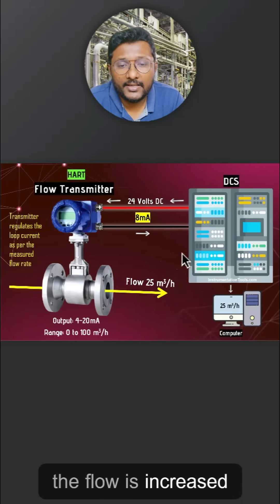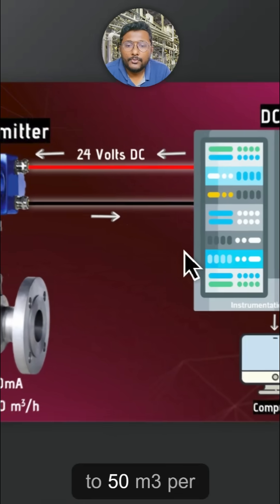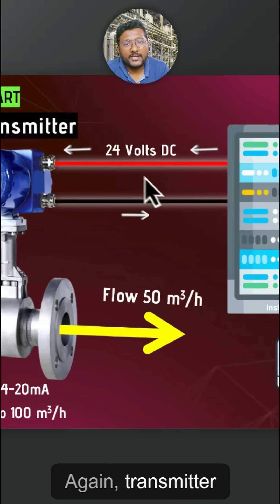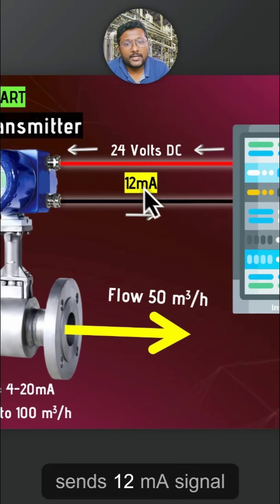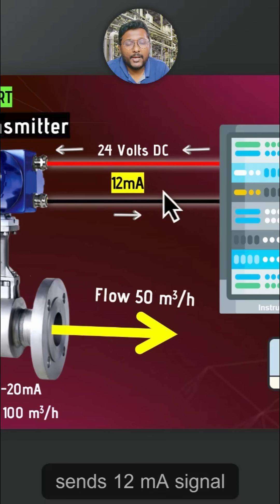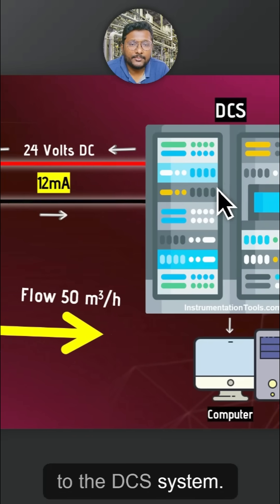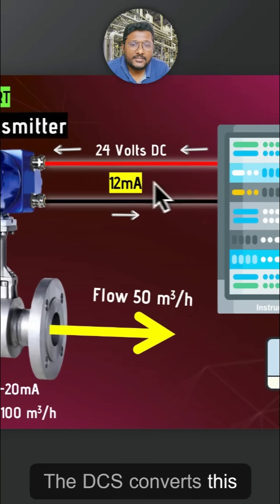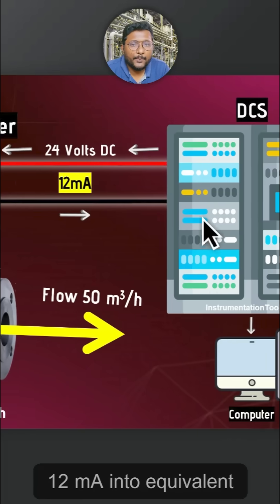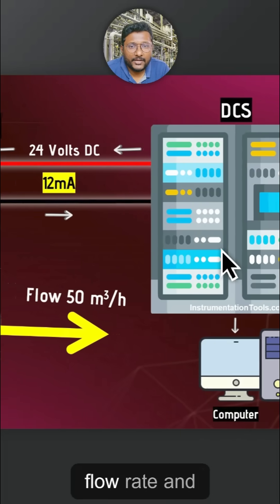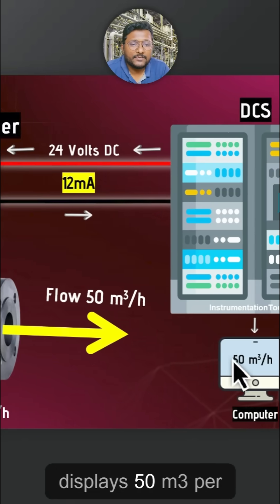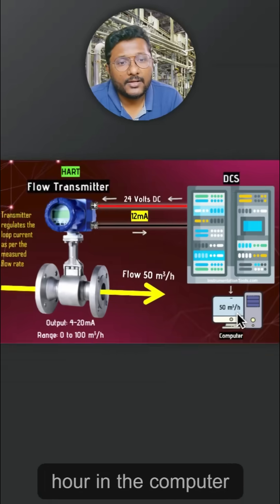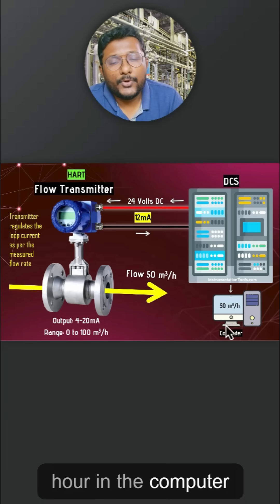If the flow increases to 50 m³ per hour, the transmitter sends a 12 mA signal to the DCS system. The DCS converts this 12 mA into the equivalent flow rate and displays 50 m³ per hour on the computer graphics.